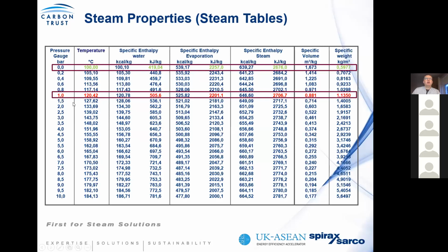to your process. But you can see that if you slide down this scale, you can pick a point. In this example, I'm just showing 1 bar, just for example. What you can see is that in this scenario, you have to increase the water temperature to 120 degrees before it will start evaporating into steam. So in other words, there's a higher energy content required just to bring water to that boiling state. You can also see that the energy required for evaporation has reduced, because there's more enthalpy in the water to flash and generate steam.